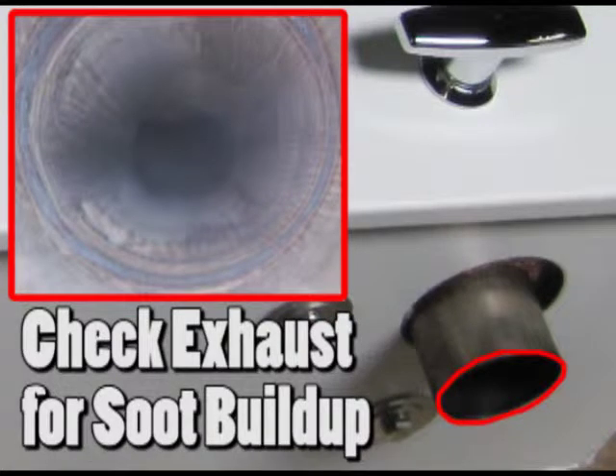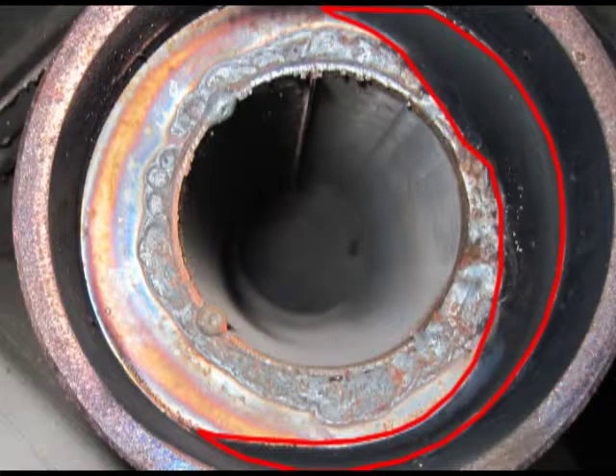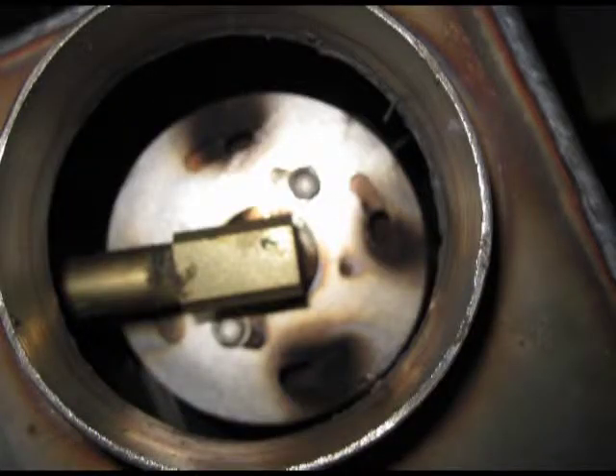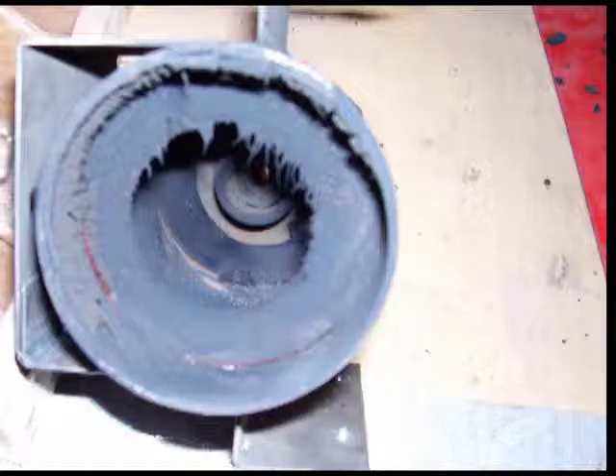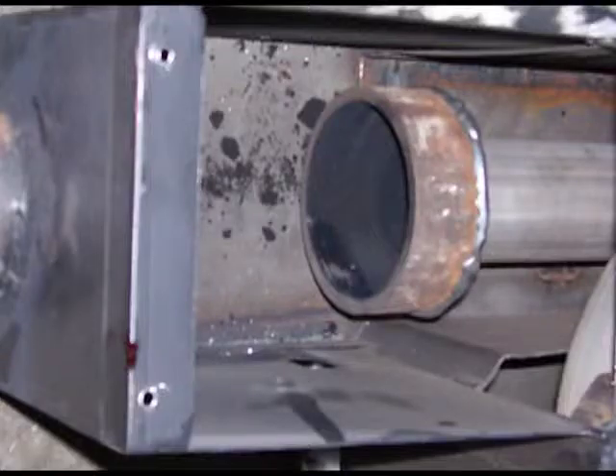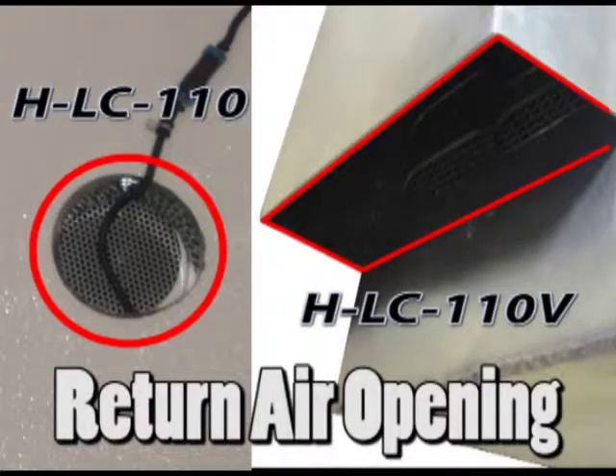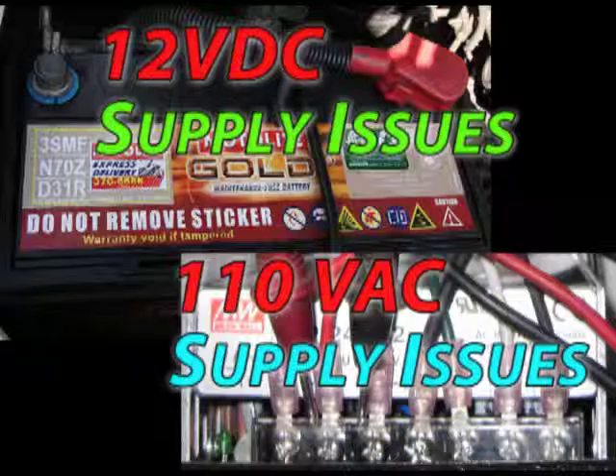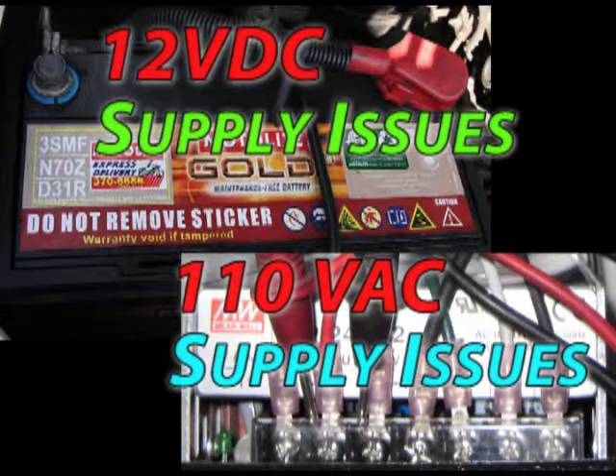Under normal use, the heater will deposit very little, if any, carbon near the exhaust outlet. These deposits are often the first sign of a problem with the heater or supply power issues. Deposits are an indication that the heater should be shut off. These deposits typically indicate that one of the openings in the heater is obstructed or the heater is not receiving enough voltage while it is running.